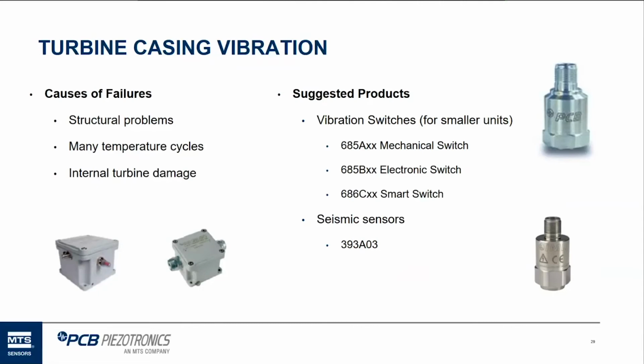Then we have what we call our 686 C series smart switches, which are software configurable. They can be set internally by software for lots of different levels. They have a relay out as well. It's just a 2-pin MIL. Again, they would need power. There's an internal relay. It's 500 milliamps. It's small, but you can hook that to an external relay that can handle a lot more power to shut down the turbine if necessary.